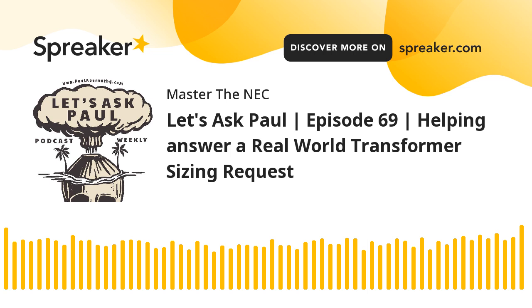And this is not an exam question, so this is the real world. I'm assuming you'll go check that out, know what you're doing, and adjust yourself accordingly. For 45 amps, it looks like I'm going to need an 8-gauge copper. And if I'm running a 70 amp one, I would need a 4-gauge copper. So again, select your poison accordingly. But they would be perfectly fine, and they would be considered protected by the overcurrent protective devices.